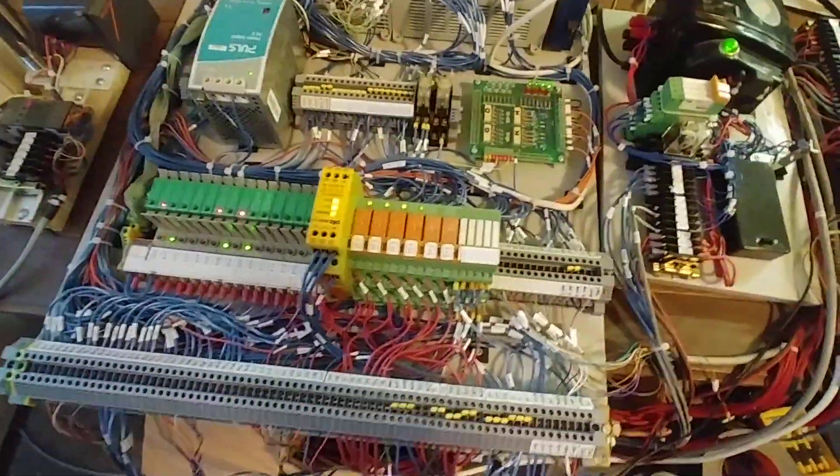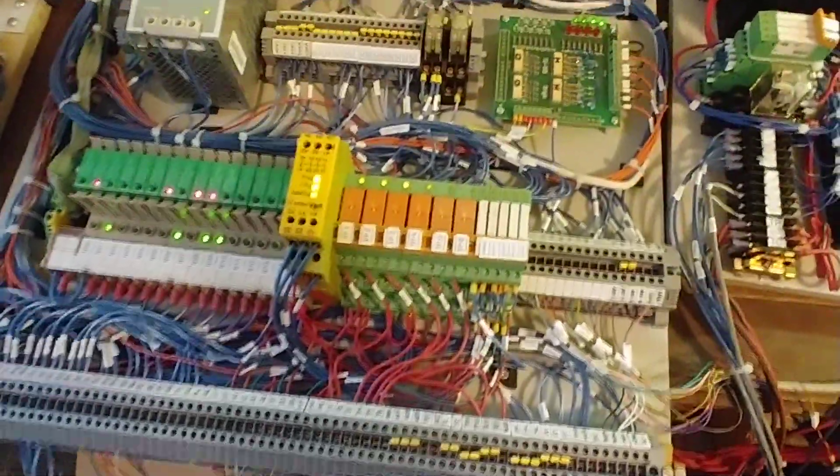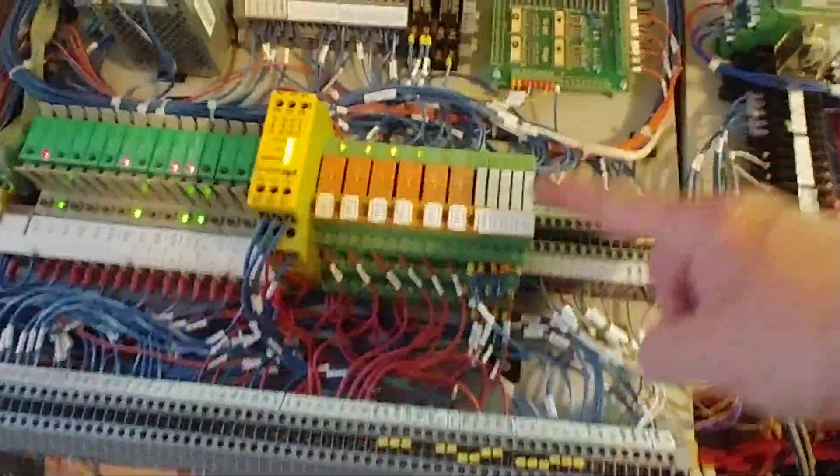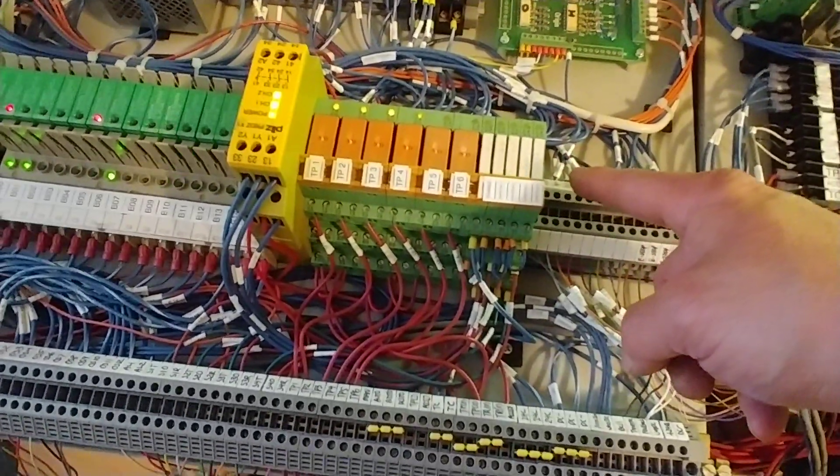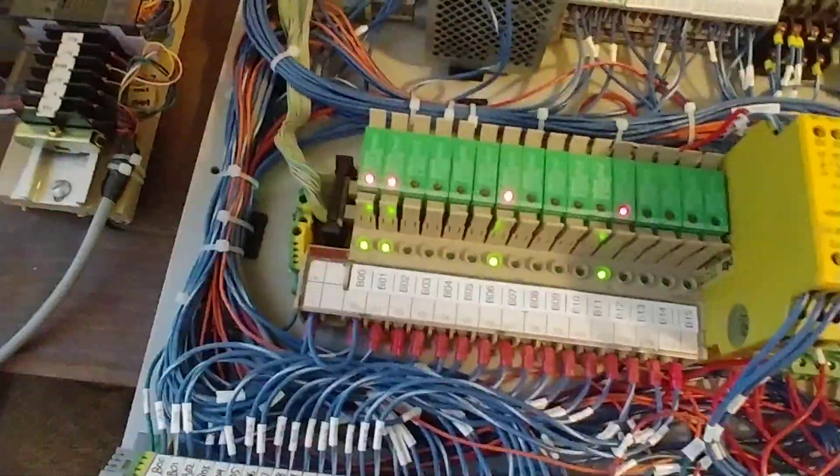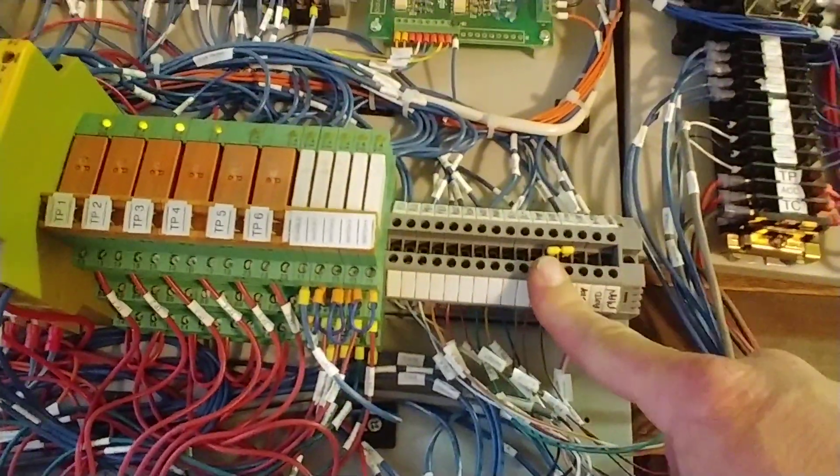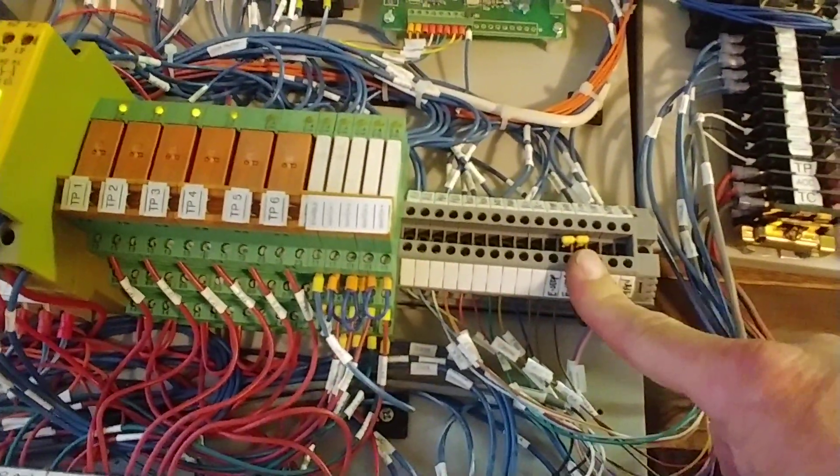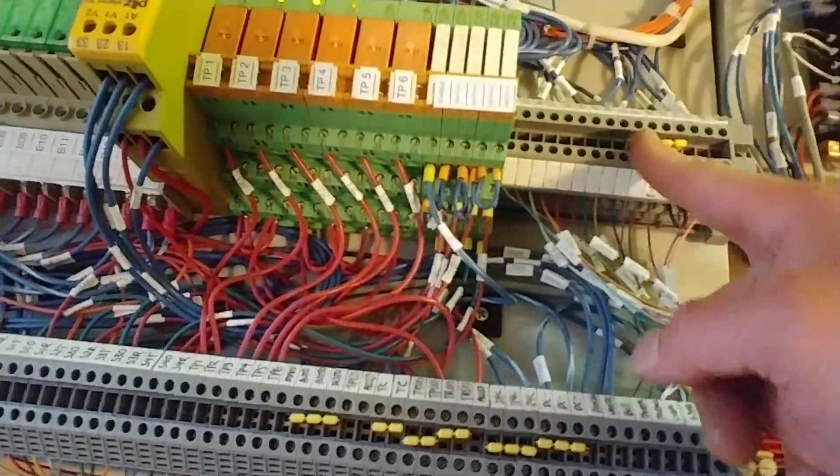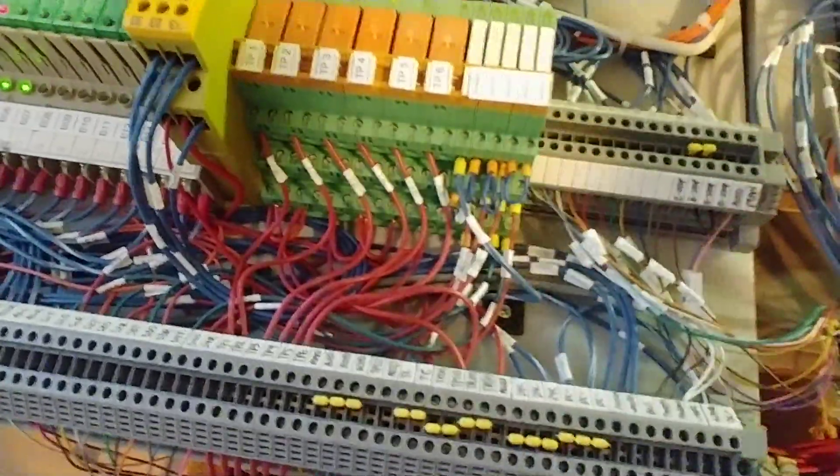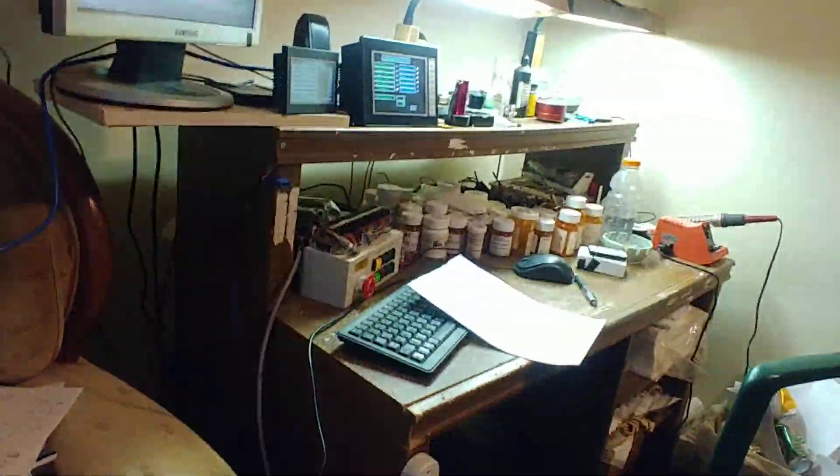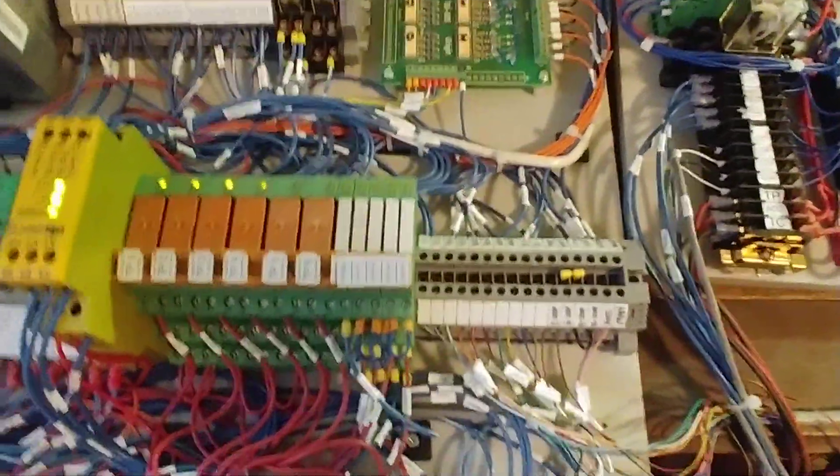Of course, the issue - another issue - is needing space. What's going to have to happen now is these five relays, I'm going to have to add three more relays here. As you can see, I don't have any space. I could probably expand the DIN rail here, but what I'm planning to do is replace these terminal blocks with double-stacked terminal blocks, which will cut this in half. This part goes out to the button box - that's the button box interface - and then I'll be able to add on the extra relays.